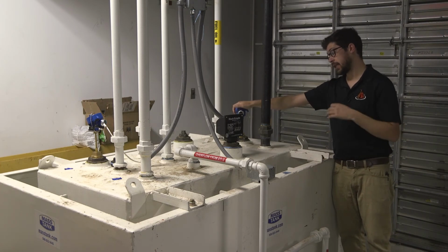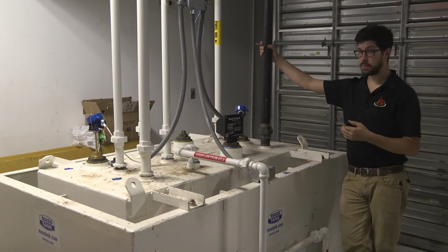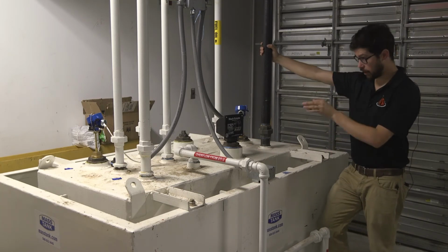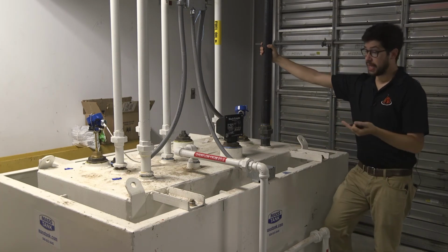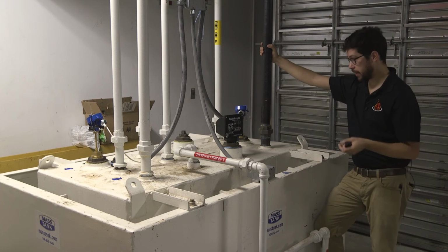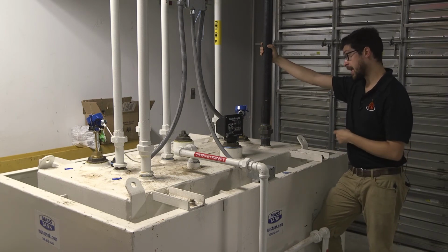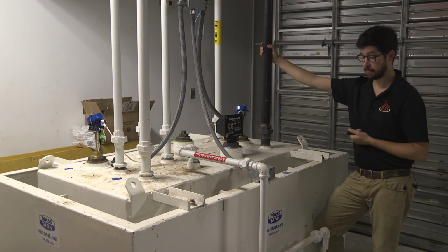So this float is connected to the new fuel oil storage tank that's out there, the new pumps, the new controller, and it's 100% identical to the other one, where it's got the high, the pump off, the pump on, and the low. And it's just simply going to feed the system from the opposite tank, the opposite pumps.